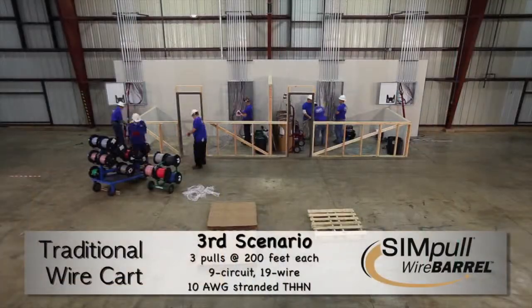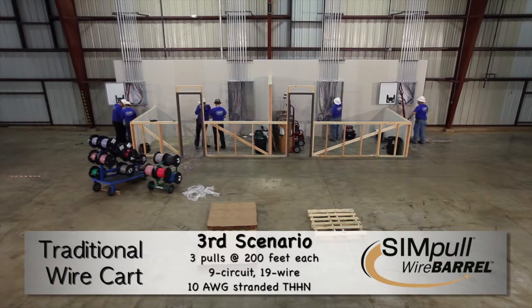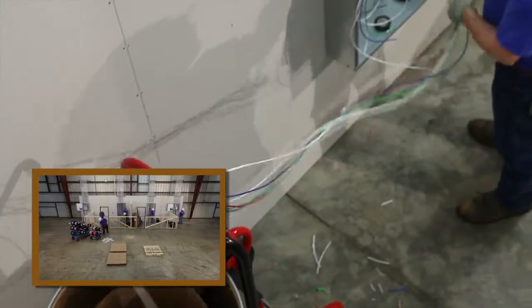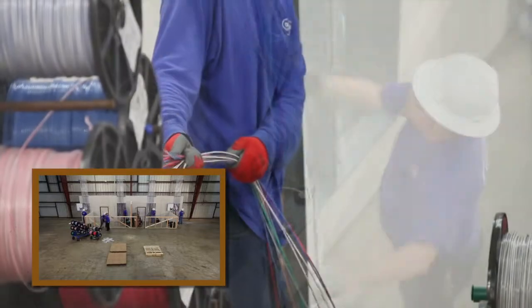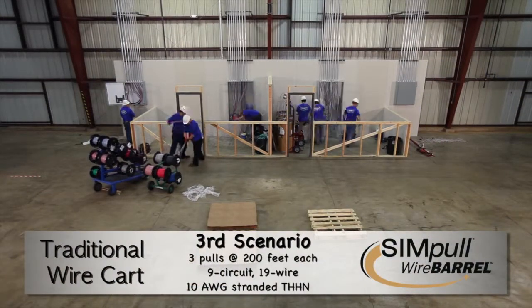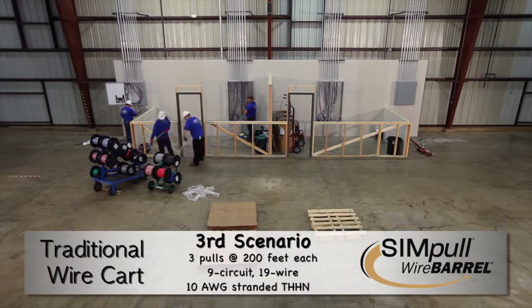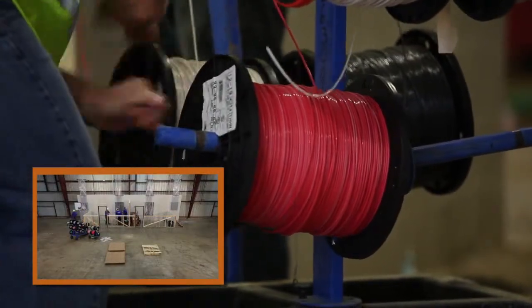This scenario clearly demonstrates how much safer and easier it is to pull the wire from the barrel versus off the traditional wire cart. The SIMpull wire barrel systems require minimal effort to pull the barrel conductors out of the wire barrel package, because the conductor weight is limited to only the conductors exiting the package and not the entire weight of all the conductors on the cart. Clean up is a breeze when using the SIMpull wire barrel. You won't end up with a room full of leftover wire reels with all different lengths, reducing your overall scrap rate. Unlike the use of traditional wire carts, you won't have to rewind the wire back onto the reels.